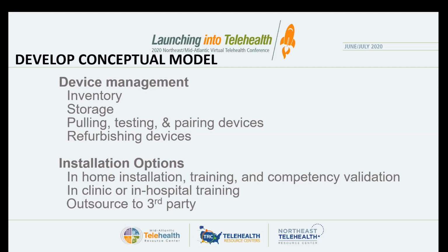When I was at Vidant Health, we cover 10 hospitals in 29 counties in Eastern North Carolina. And so we made a decision there that biomedical department, we paid for biomedical technicians to receive inventory, to store, to test, to pull, etc., and do all the refurbishment of the devices.